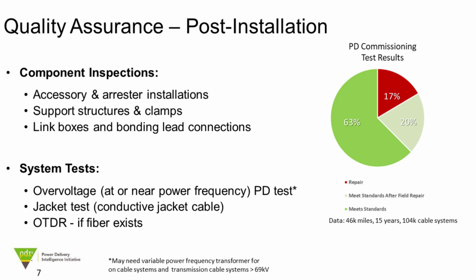The way these are tested, they use a relatively high voltage, so even a small scratch or damage in one local area would not result in false negatives. So they can be scratched, but they would still continue to perform their function. But I would not be able to provide a specific number. I think you just answered a question that just came in, and the question was whether minor damage on the outer sheath during installation can lead to failure of cable during service. So that was another good question from a utility.